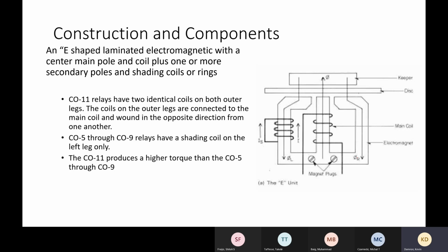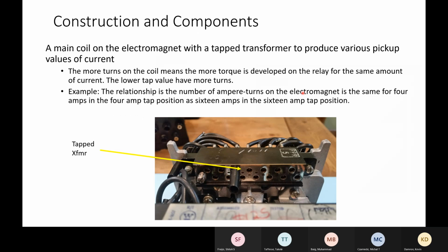So if you actually looked at the relay, it's kind of an E shape. Let me switch back to my pointer. So you've kind of got this E shape laminated disc. And whether it's a CO11 or a CO5 will depend on whether it has both of these outer legs or just the one. So if it's a CO5 or 9, it doesn't have this right curve. And here's the disc that you typically see. I can share this with everybody later, but when we talk about the tap, it's really what you're doing. You're tapping the transformer in the relay, and what it's doing is creating an amp-turn ratio within the relay to cause it to operate.